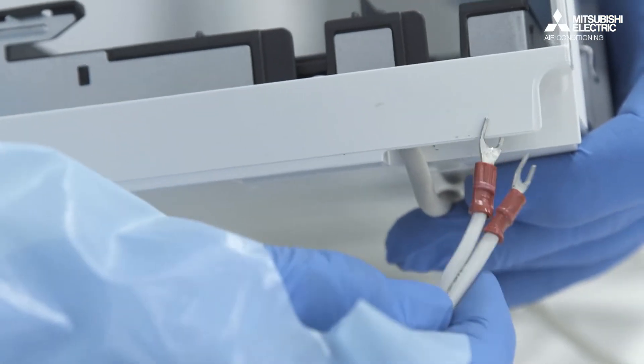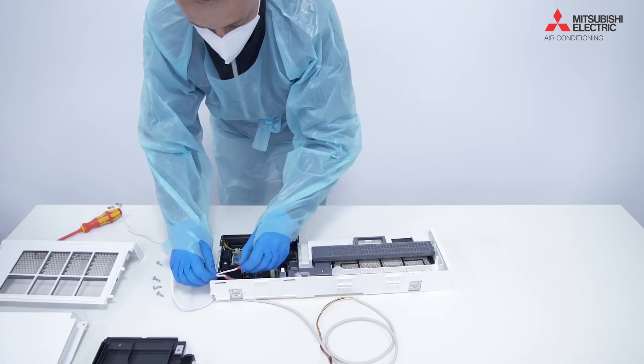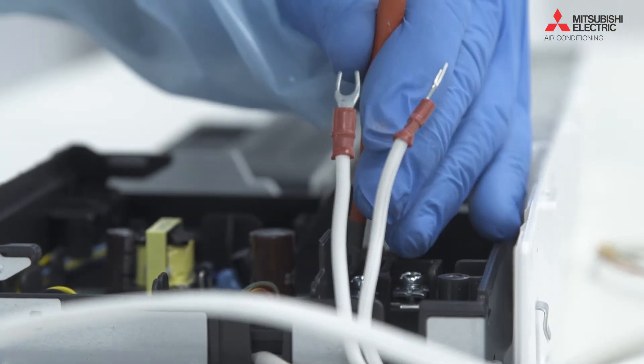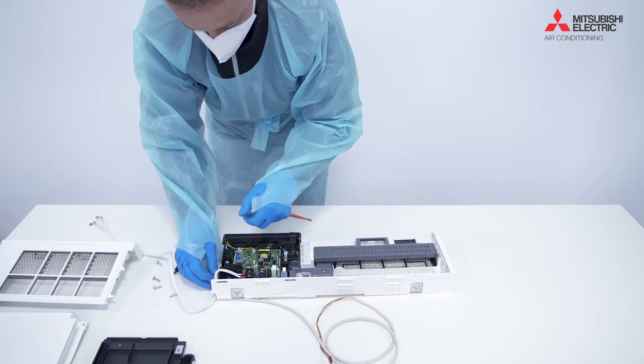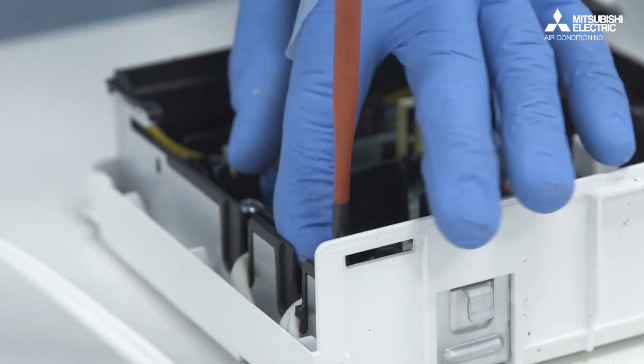The only time you may need to get into this board would be if you've got another piece of equipment that's using the CN105 connection currently on the indoor board. There's another CN105 connection on this board here, so for example if you're using MELCloud on the CN105 connection on the indoor board, we're going to take that connection off there and reconnect it into here.